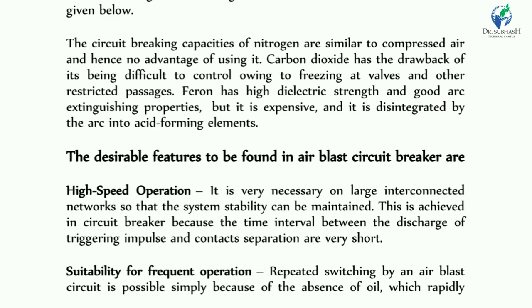The desired features to be found in air blast circuit breakers include rapid arc extinction. This is very necessary on large interconnected networks so that system stability can be maintained. This is achieved in the circuit breaker because the time interval between the discharge of the triggering impulse and contact separation is very short.